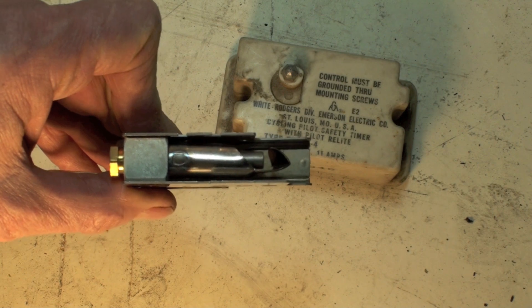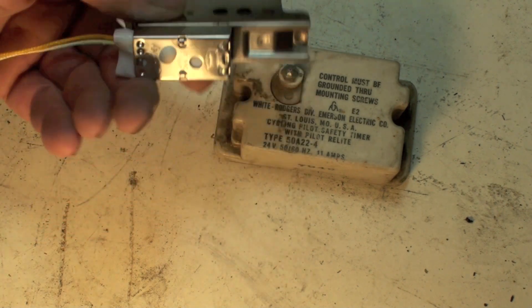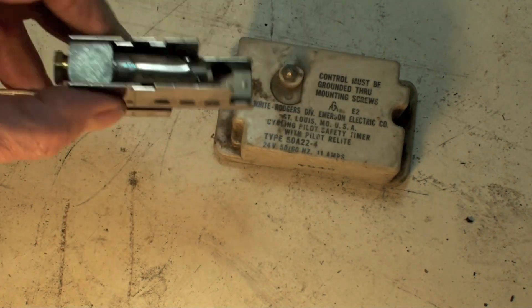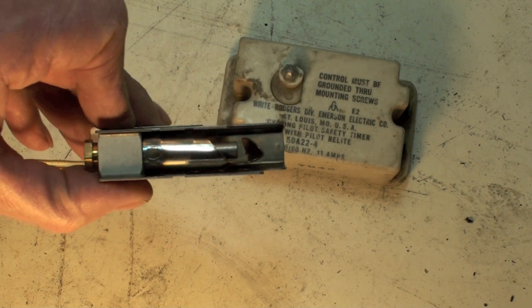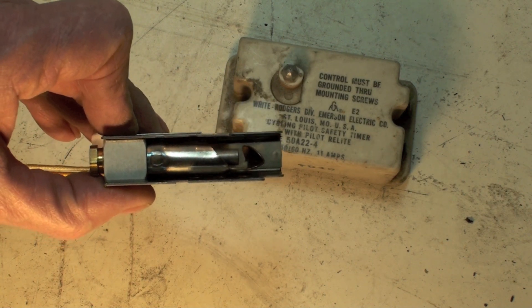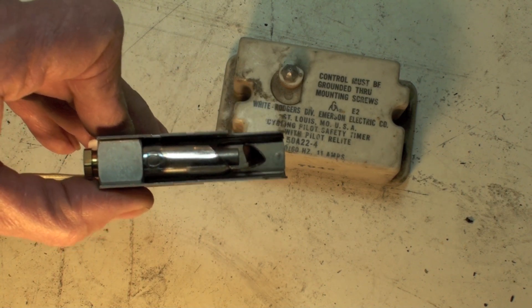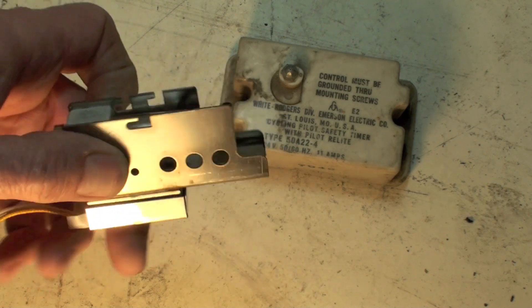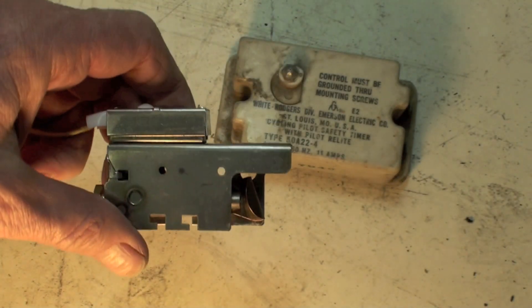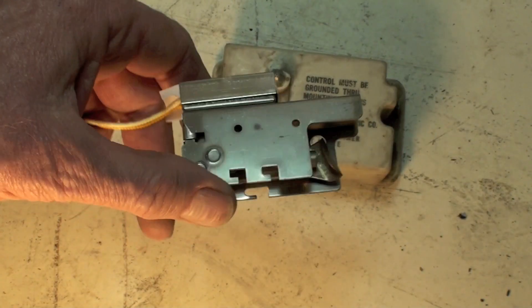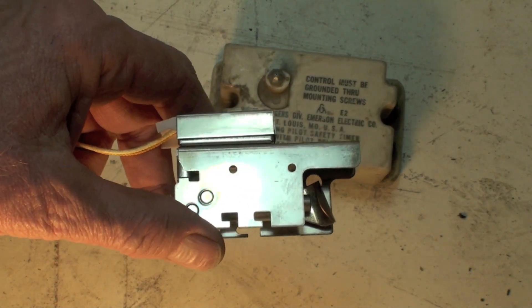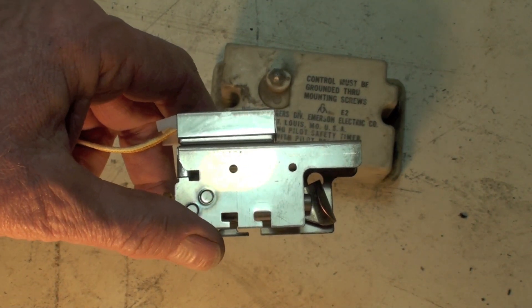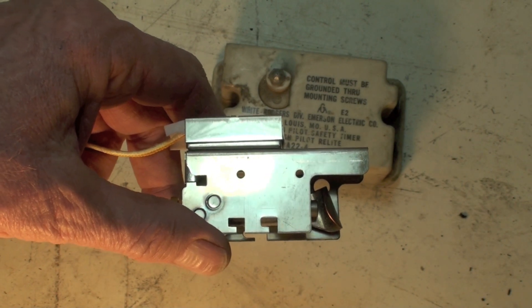Just a very simple one. There's another one of these that has three wires coming out of it. If I can manage to come up with one of those I'll go over it. For troubleshooting, very commonly they will stick and they won't make. If you tap the thing with a screwdriver and it lights off, then that was your problem.